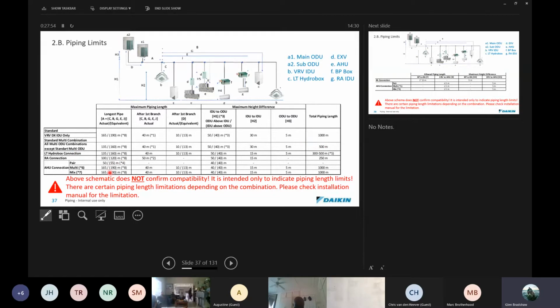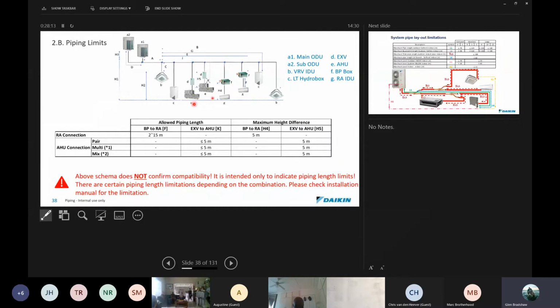All right, and then of course, just to get on to some other measurements, we also can use RA units. These are non-VRV indoor units in conjunction with BP boxes. These also affect, and I'm going to show you as we move on to one of the other slides, some of the things you need to keep in mind for that. Here we've got that over here again, and something we need to consider here. We're looking now at something which has become popular, our expansion valve kits, which connect onto air handling units. And when using these, we must also consider a maximum length between the kit and the unit of 5 meters, and a maximum height also 5 meters.